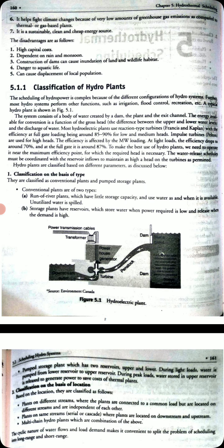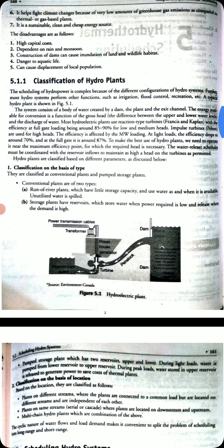So to make the best use of the hydro plants, we need to operate them near the maximum efficiency point, for which the required head is necessary. The water release schedules must be coordinated with the reservoir inflows to maintain the high head on the turbines permitted.